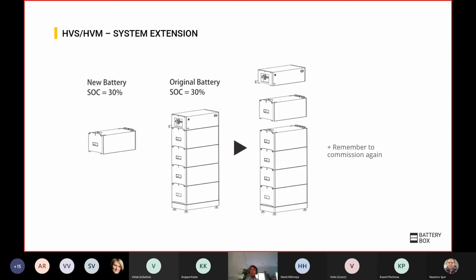A very important thing to mention. I've highlighted a few times that it is possible to add batteries later on. And it is very important because these systems are connected in series, meaning that the same current will be going through all the batteries. So all the batteries must be at the same state of charge. If you're adding one new battery and the system is at a different state of charge than the new battery, you are going to lose capacity. You will see state of charge jumps.